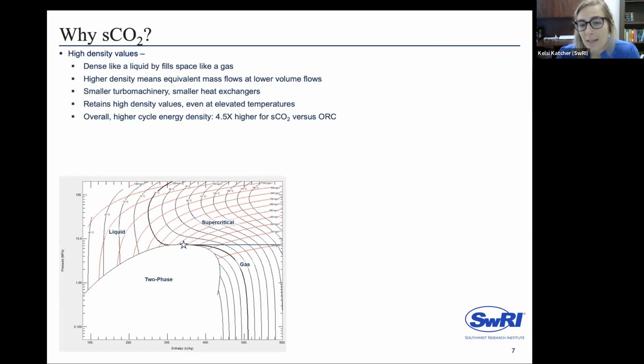Also, CO2 retains high density values even at high temperatures. So even on the hot leg of your power cycle, upstream or downstream of your turbine, you can still have small line sizes, and you don't have to have these massive pipes that you would have, say, in a steam system or any other gas system. Overall, this means the energy density of CO2 in the supercritical state is higher. Comparing to ORC fluids, we're about 4.5 times higher energy density.